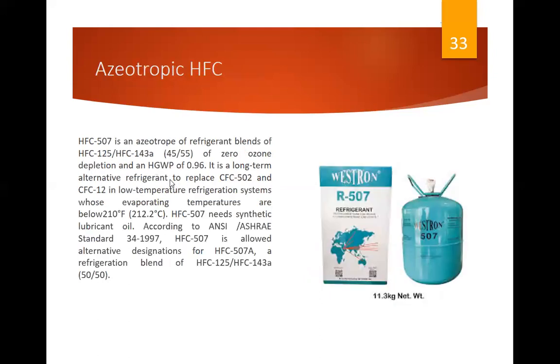Next, Azeotropic HFC. HFC 507 is an azeotrope of refrigerant blends of HFC-125 and HFC-143A, 45 to 55%, of zero ozone depletion and an HGWP of 0.96. It is a long-term alternative to replace CFC 502 and CFC 12 in low-temperature refrigeration systems. Whose evaporating temperatures are below 210 Fahrenheit to 212 C. HFC 507 needs synthetic lubricant according to ANSI ASHRAE standard 34-1997. HFC 507 is allowed alternative designation for HFC 507A, a higher refrigeration blend of HFC 125 and HFC 143A, 50/50.